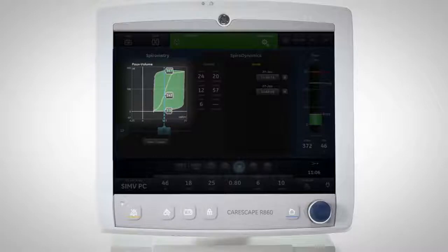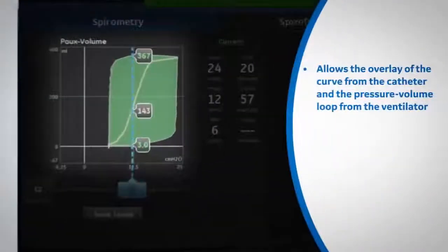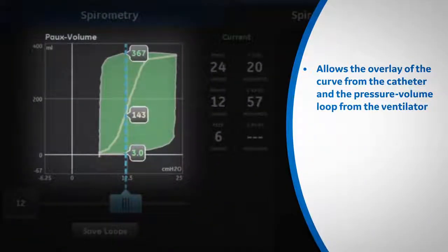The curve represented using the SpiroDynamics tool allows for easier visualization of the upper and lower inflection points. The CareScape R860 allows the overlay of the curve from the catheter and the pressure-volume loop from the ventilator.